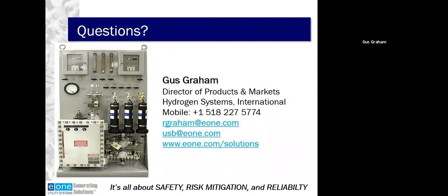So when you call in for your replacement cell, we may ask you to go in and get the software version of your machine to ensure compatibility first, that we have two styles of cells. And also to that exact question, if you need to type in that purity compensation value, which is available only on the newer software versions. And when I say newer, 10 years. So in this industry, new is 10 years old.